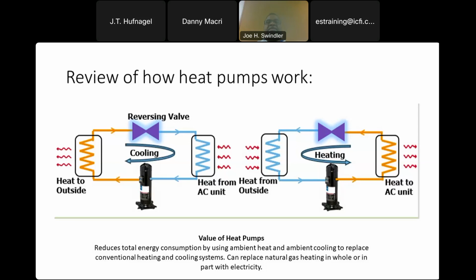On the other hand, for heating using a heat pump, there's a reversing valve, and the heat of compression is dumped into the plant, and that heat heats up the interior of the building. And so that's the difference. The decision of which mode it is in is based on rejecting the heat to ambient for cooling or rejecting the heat inside for heating. Next slide.